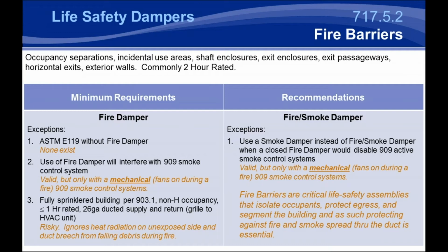And basically the first few exceptions you will see throughout Section 717. So the first exception, ASTM E119, is basically the way you test a fire-rated barrier. If you test a fire-rated barrier with a penetration without a fire damper, and it makes sure to stop the fire from spreading through that penetration without the fire damper, there's a heat load that they look at and flame spread. You can pass that barrier without a damper. The reason that exception exists is that it allows for innovation in the industry. It allows for people to test new and innovative products to protect barriers, and that's basically how innovation is allowed.